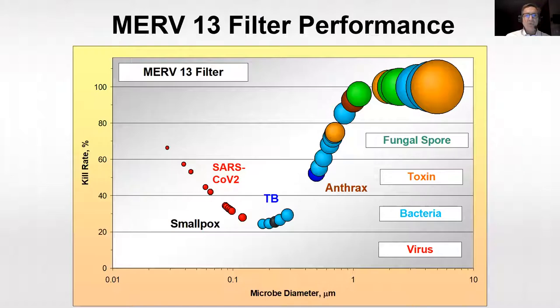Now let's look at a MERV 13 filter, which is probably the optimum for our case. It still lets a lot through. The SARS-CoV-2 virus is about 0.1 micron, so if it floats up in the air, that's what you can get. You're getting about 40% catch on something that's 0.1 micron. It's not so good. It's good on larger stuff, 1 micron and more, and it's good for the very small, but in between, like every filter, it's got its weakness.